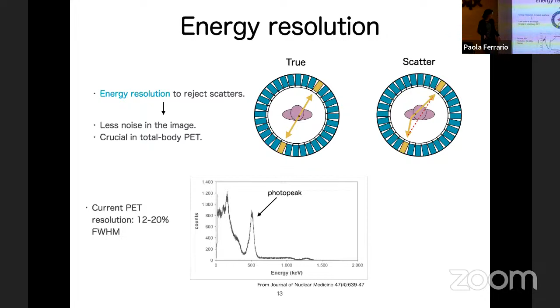So if you have a good energy resolution, what happens? When a photon makes a Compton scatter in the body, it loses some of its energy. So the photon that you detect in your scintillating crystal has a lower energy. This is an example of a conventional PET scanner, and this is the distribution of the energy of the gammas. If you have better resolution, this peak is narrower, and you can reject more Compton scatter in a more efficient way. The current energy resolution of conventional scanners is between 12% and 20% full width at half maximum. This is what crystals provide you.